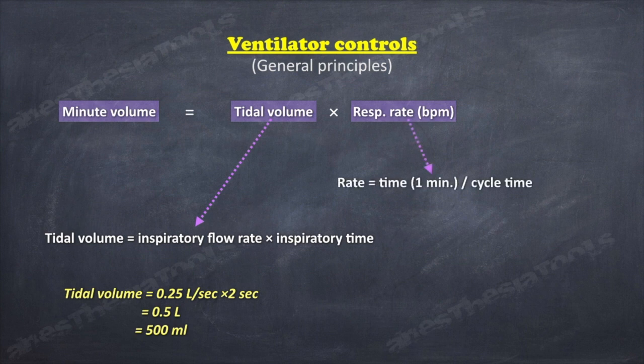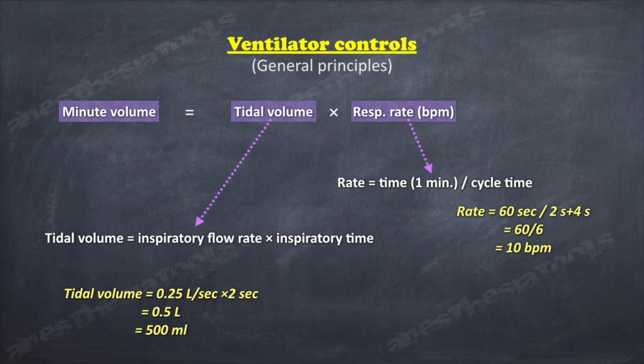The rate is derived from the cycle time and expressed as the number of complete cycles per minute. For example, if the inspiratory time is 2 seconds and the expiratory time is 4 seconds, then the total breath time is 6 seconds. So the rate equals 1 minute or 60 seconds divided by 6 seconds, that is 10 cycles per minute.